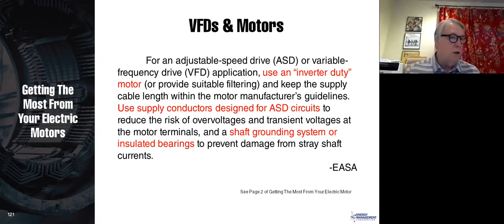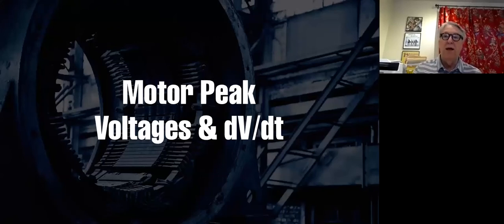Now, this is right out of your booklet. For an adjustable speed drive or variable frequency drive application, you should use an inverter duty motor. We've talked a little bit about what an inverter duty motor is. There should be something on the nameplate or in the cut sheet that says that motor is going to run on a PWM drive, and it should meet NEMA MG1 Part 31. Next, use supply conductors designed for variable frequency drive circuits. They call them adjustable speed drives. Now, we will get into this in a moment. Most people do not do that, but we will talk about that. And finally, use your shaft grounding system. So EASA says anytime you have a motor on a drive, you should have these three things: inverter duty motor with a shaft grounding system or insulated bearings, and use ASD supply conductors.